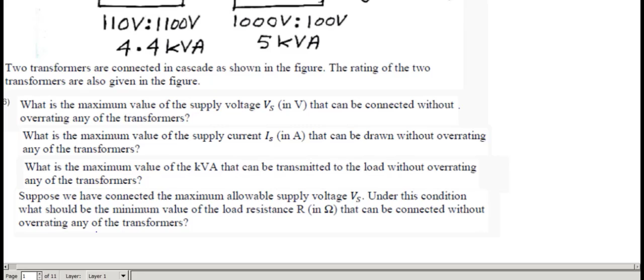This is the first transformer, primary side, and this is the second transformer, secondary side. First let's find the current here and there. 5000 by 100 gives 50 amperes flowing in the secondary of the first transformer and secondary of the second transformer. Primary is 5000 by 1000, giving 5 amperes here and 5 amperes here.